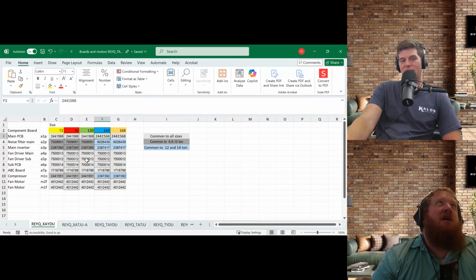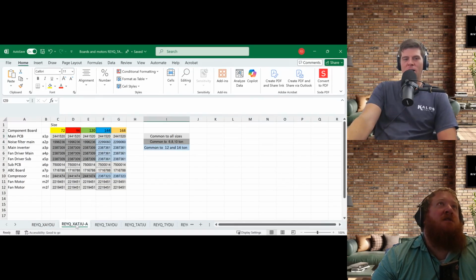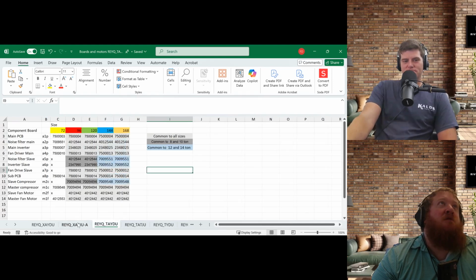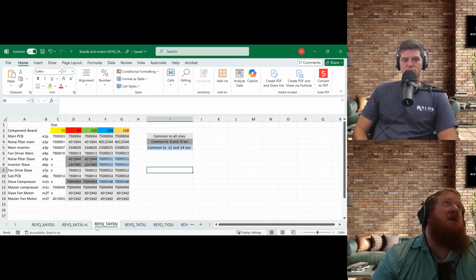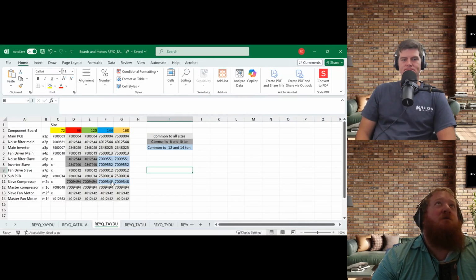This was something I did to help organize when we needed a specific compressor. I could say, okay, do we have anything on our shelf that's the same for the REYQ TAYDU? Let me check - compressors, where are they at? There's our compressors right there. So I could technically use a compressor from a 96 in the 120. It's the same compressor. Same with the 144, 168 - same compressor.